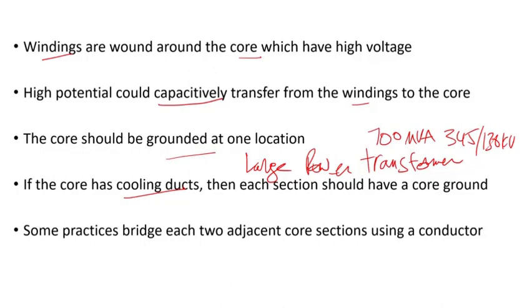So what they would do is insert cooling ducts, and I think I have a picture that I will show what I mean by that, so that oil can circulate in between sections of the laminations. The manufacturer will perform simulations to see what is the most cost-effective way of addressing any localized heating in the core. If you have cooling ducts, they're going to put two sections isolated from one another. So then each section should have a core ground.